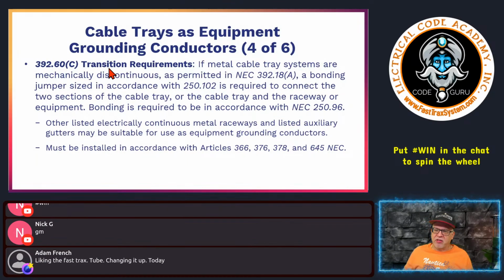392.60(C) talks about transition requirements. If metal cable tray systems are mechanically discontinuous, meaning it's not one continuous run and has sections that you have to connect together, as permitted in 392.18(A), a bonding jumper sized in accordance with 250.102, which we kind of talked about, is required to connect the two sections of the cable tray, or the cable tray and the raceway or equipment. Bonding is required to be in accordance with 250.96. Again, just like you would do with feeder raceways, this should be common sense, tying all metal parts together.